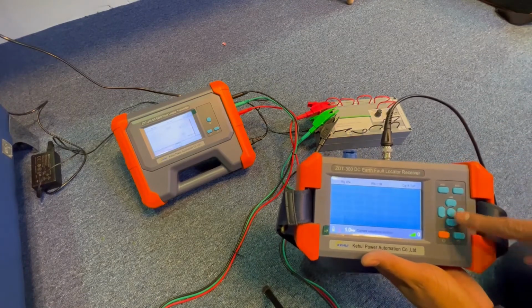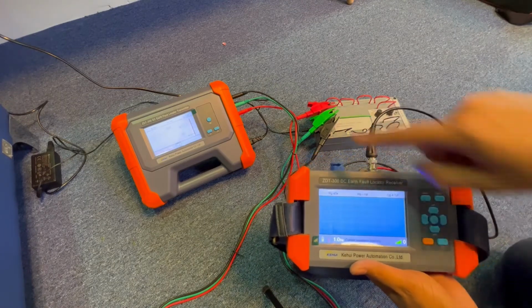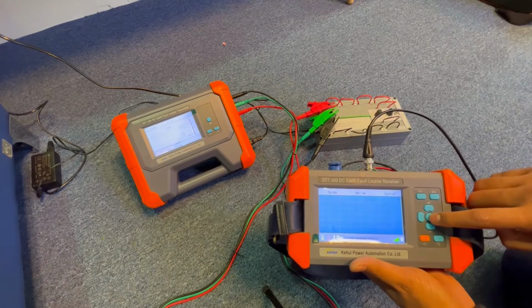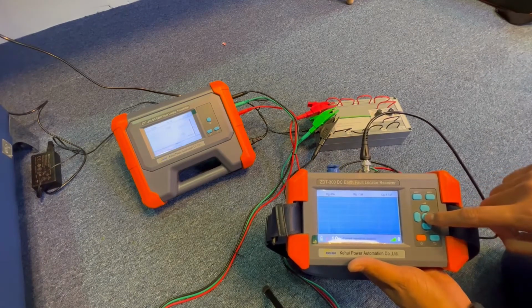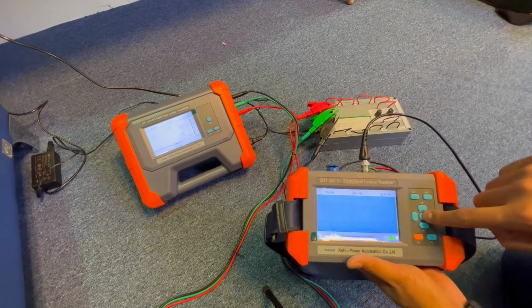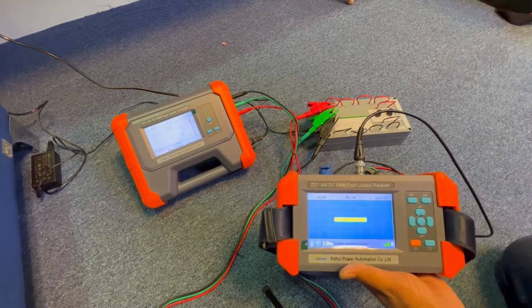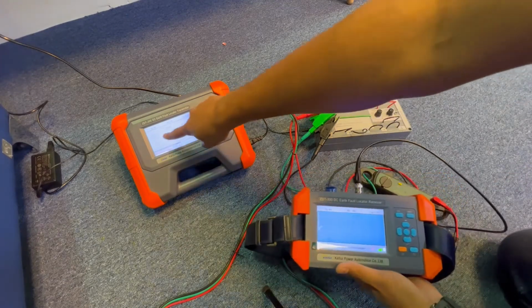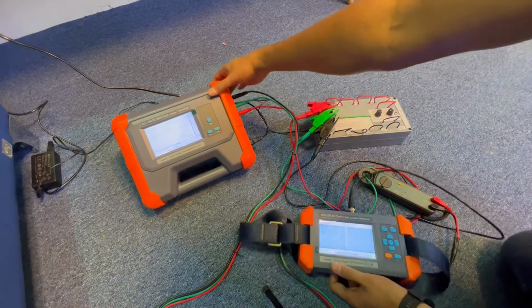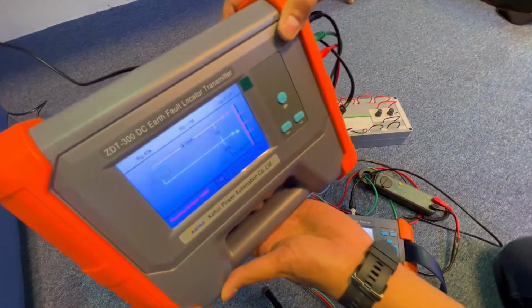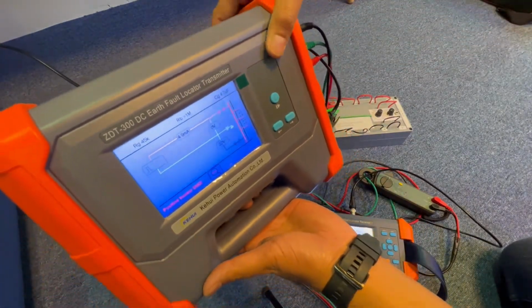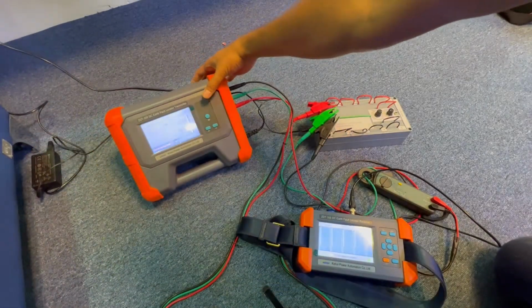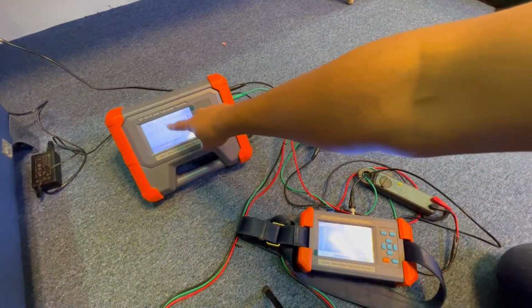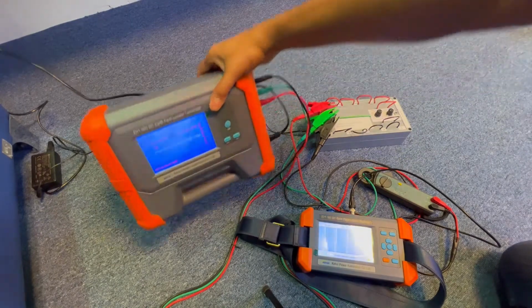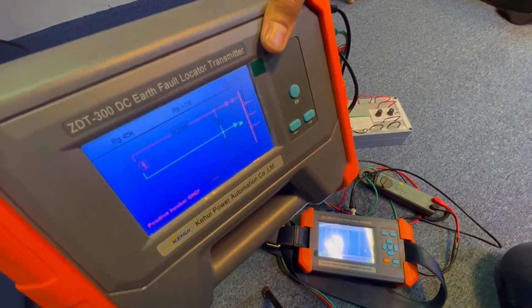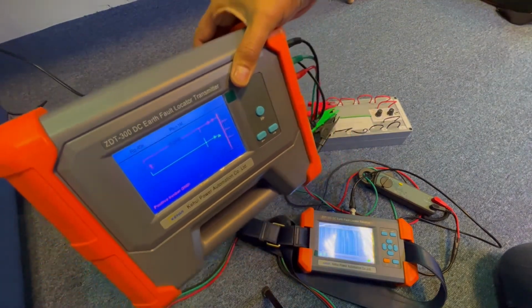So now just start the transmitting. The injection of the transmitter starts from the receiver, so you ask the transmitter to inject the signal. You can see that there is an indication on the receiver stating that the signal has already been injected. You can see the leakage current as well, the leakage current that we inject into the system. This is not the leakage current in the main DC-DB system.